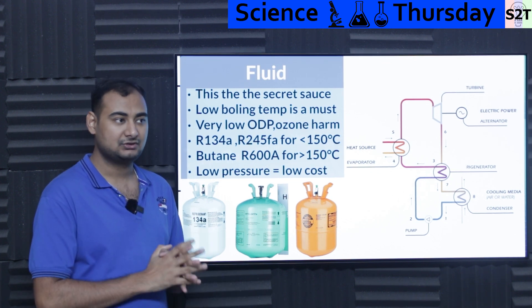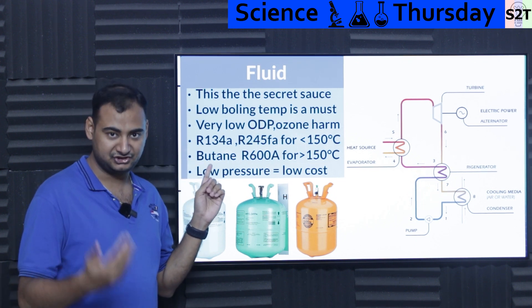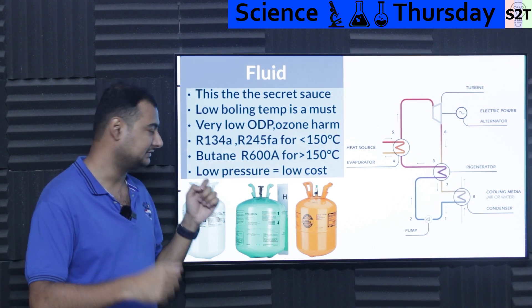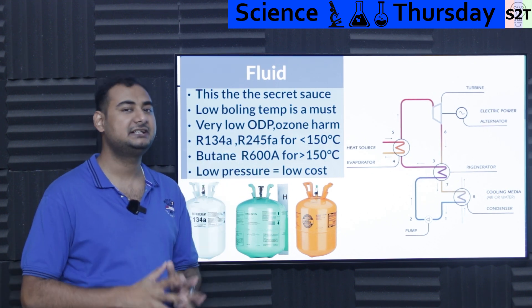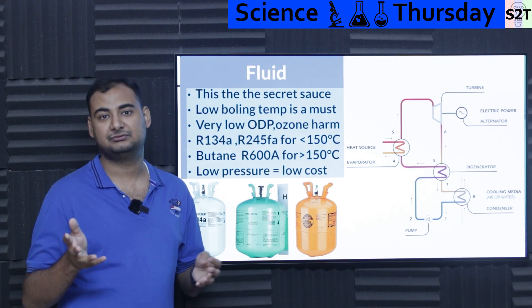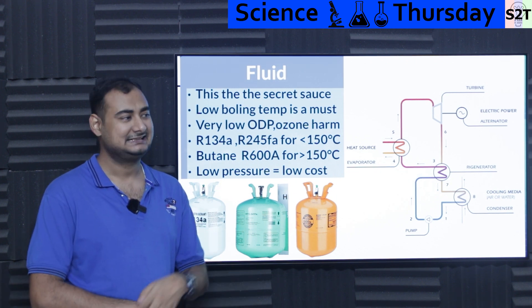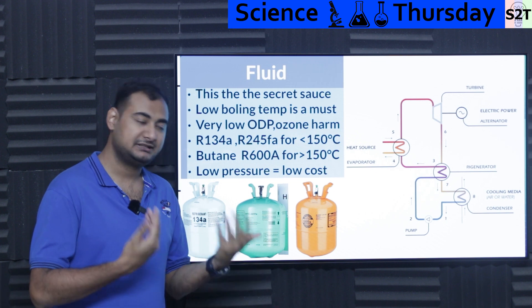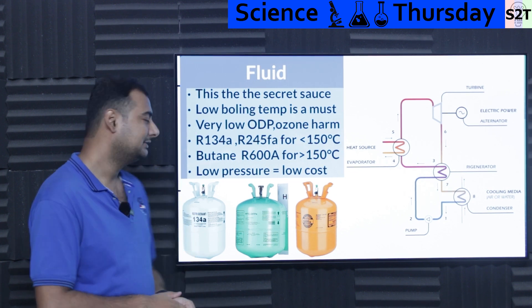Most components are common, but pressure requirements differ. For example, a generator using R134a might give you 10 kilowatts of electrical energy but requires piping designed for 15 to 50 bar. R245fa might give you only 8 kilowatts, but the pressure requirement drops to 5 to 10 bar, making the overall system exponentially cheaper. In high electricity-cost regions like Germany, users might accept the higher pressure cost for extra output, but most will prefer the cheaper 8-kilowatt option.